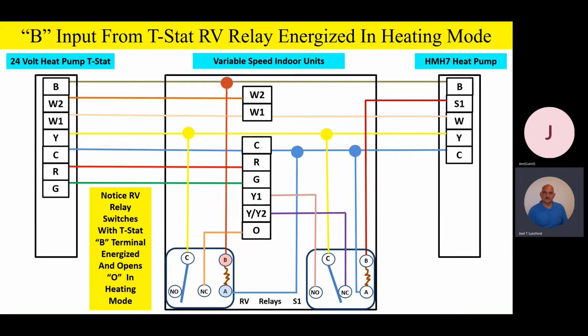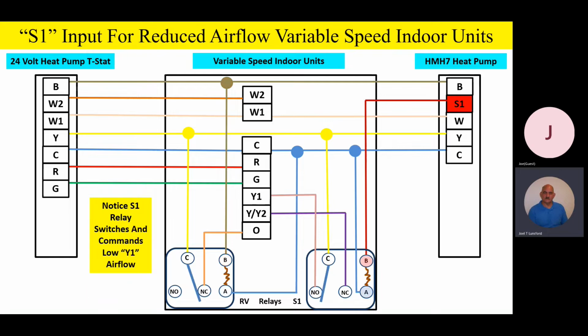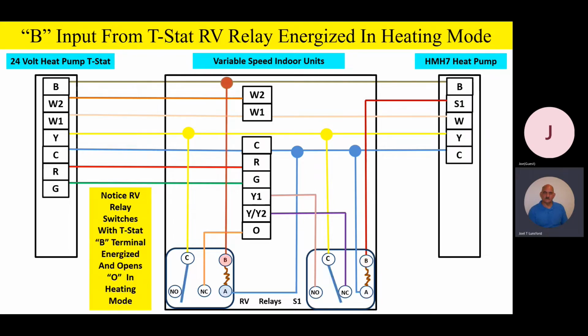So as you take a look at that animation again, let me do that again real quick on that RV relay. Watch it closely. Bang, we switch it in the heating mode. When we go to the heating mode on the thermostat and we energize the B terminal, it energizes that RV relay and it takes 24 volts off of that O terminal. That's the only reason that RV relay is there, is to take 24 volts off of the O terminal on our variable speed products in the heating mode. Any questions or comments on how these relays are working with our indoor product? Everybody good?